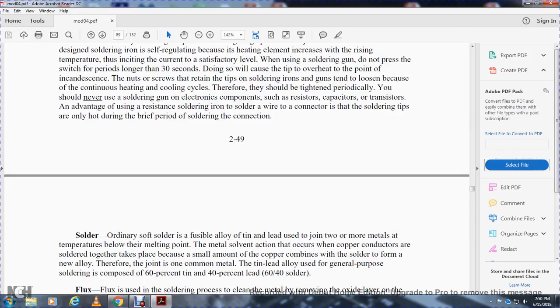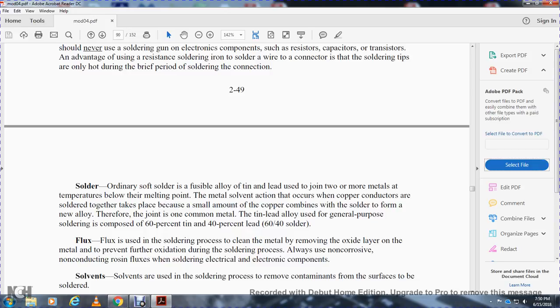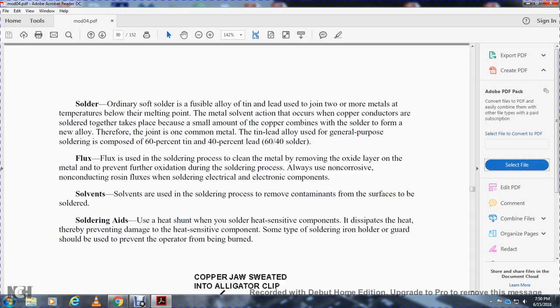Only soft solder, a fusible alloy of tin and lead, should be used to join two or more metals at a temperature below their melting point. Metal solvent action occurs when copper conductors are soldered together. This takes place when a small amount of copper combines with the solder to form a new alloy at the joint. The most common soft solder is the tin-lead alloy composed of 60% tin and 40% lead. Flux is used in the soldering process to clean the metal by removing the oxide layer and to prevent further oxidation during the soldering process. Always use non-corrosive, non-conductive rosin flux when soldering electrical or electronic components. Solvents are used in the soldering process to remove contaminants from the surface to be soldered. Soldering aids such as heat shunts dissipate heat, thereby preventing damage to heat-sensitive components. Some types of soldering iron holder guards should be used to prevent the operator from being burned.